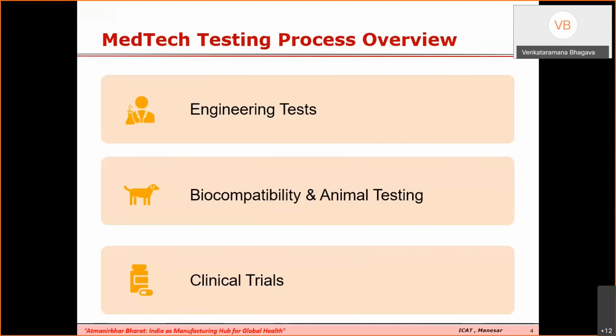Yes. So in this slide, I have tried to capture the entire MedTech testing process. So they fall under three categories. The first one are the engineering tests. Second ones are the biocompatibility tests. So biocompatibility means essentially something has to be compatible with our body. So you have got tests such as cytotoxicity, sensitization, irritation, and so on. And along with that, you have got animal testing.